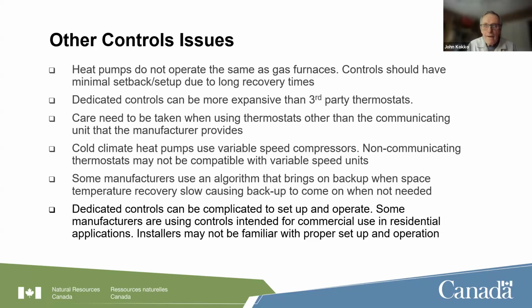There are some manufacturers where it is a communicating thermostat, but what it looks at is not one of the strategies that I talked about today, but rather it looks at how fast the space is recovering and brings on the backup when the space isn't coming up quickly enough. And I've seen that this brings on the backup heat at the strangest times for the strangest reasons and is not a very energy efficient strategy at all. And these controls can also be somewhat complicated to set up. So we want to be careful that when the installers are putting them in, they have been factory trained basically and are able to set those up properly.